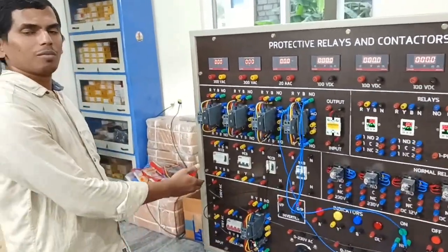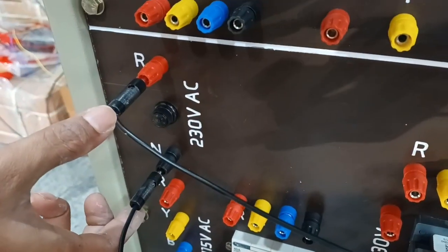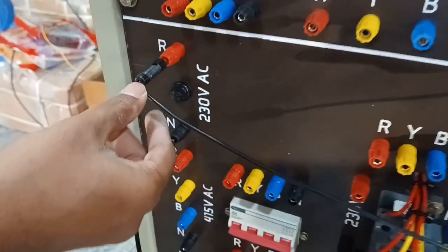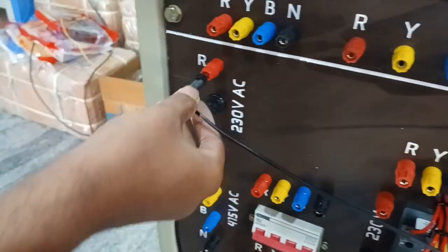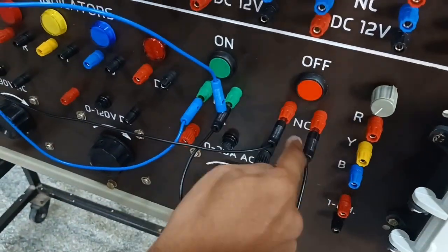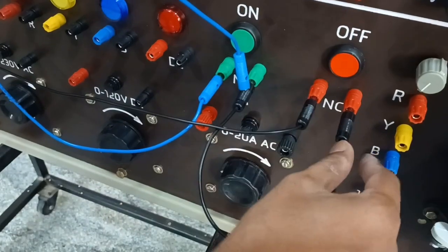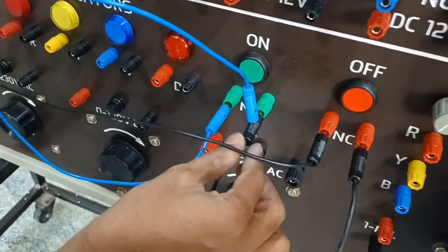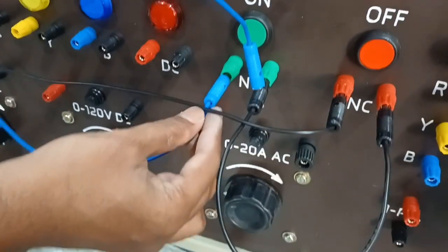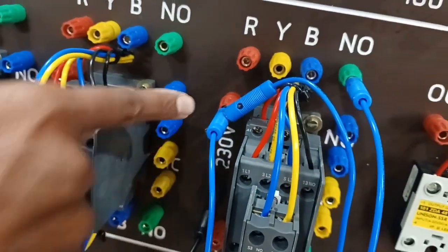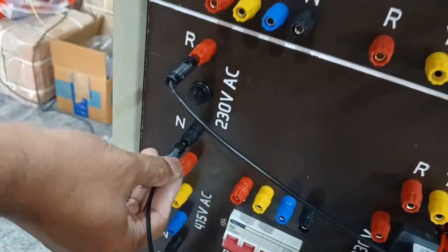Now we can have basic contactor wiring. Now we are taking single phase supply from here. This is phase, this is neutral. My single phase wire is connected to one end of the push button NC terminal, and the other end of the NC is connected to one end of NO, and the other end of NO is connected to the contactor coil phase terminal, and the contactor coil neutral is connected to the supply neutral terminal.